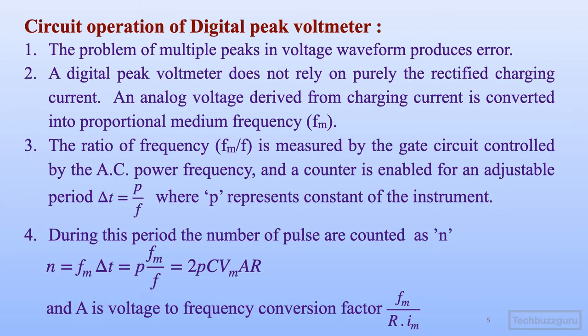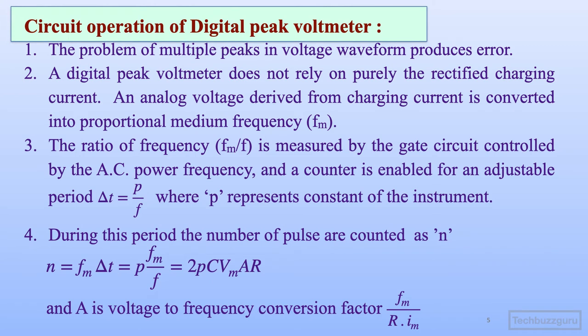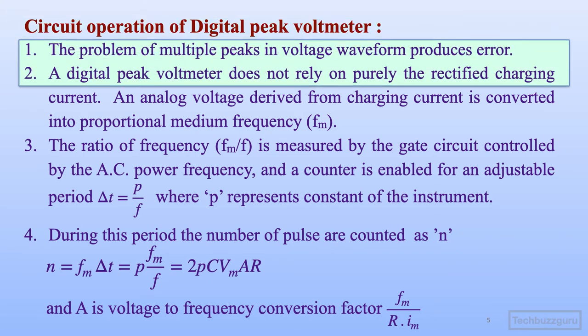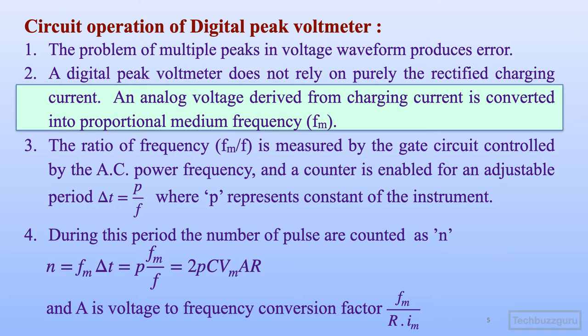This is how the digital peak voltmeter works. The problem of multiple peaks in the voltage waveform produced errors with the series capacitor peak voltmeter method, so digital peak voltmeters are used to overcome that. Digital peak voltmeters do not rely purely on the rectified charging current; rather, an analog voltage is derived from the rectified charging current and converted into a medium frequency represented by FM.